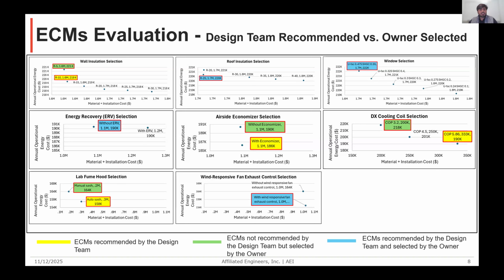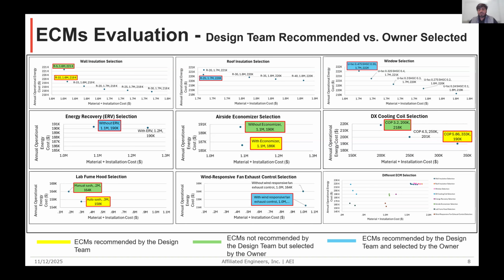So here in this chart, I have shown the variation of annual operational energy cost with first cost for all the variations of each ECM. I've highlighted the ECMs that were recommended by the design team with yellow. Green is showing the ECMs that were not recommended by the design team but selected by the owner, while blue is showing the ECMs that were recommended by the design team and also selected by the owner. I'll also add that these ECMs were not evaluated just as individual measures. As you can see in the bottom right chart, I've shown the variation of the same variables for all of the ECMs together as a whole.